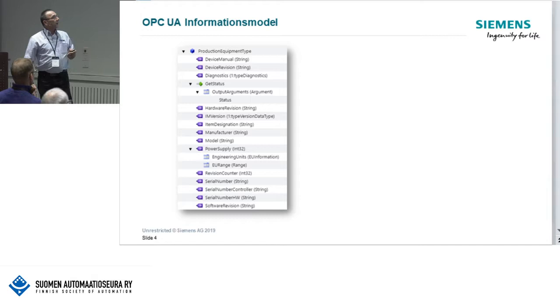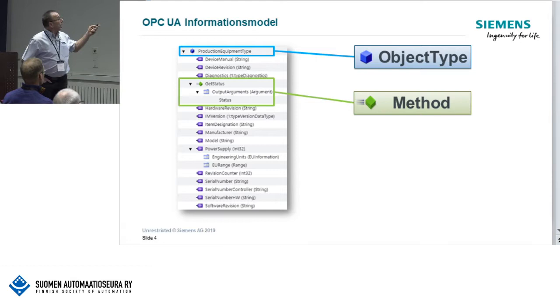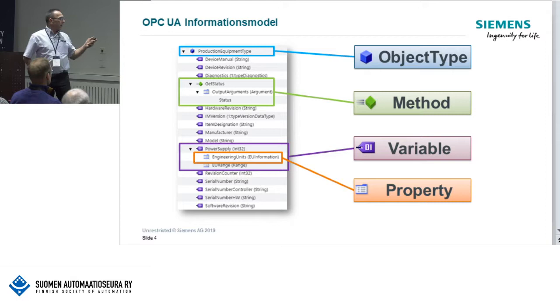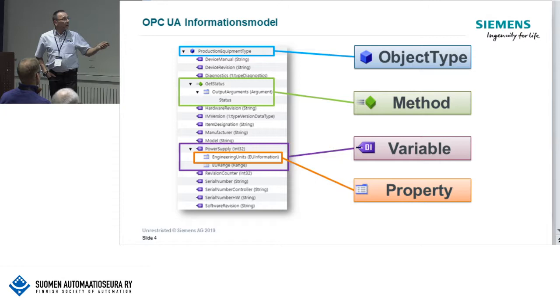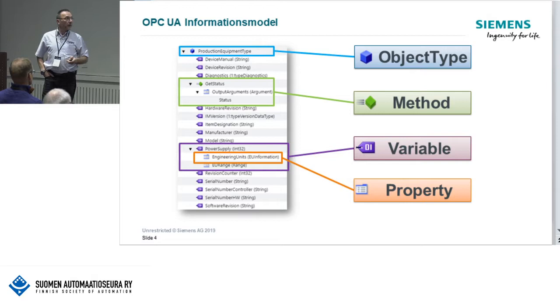In the information model it looks like this: here I take an example — we have a production equipment type, which is an object type. On this you get methods, variables, and of course you can define properties. These properties also carry meaningful information like engineering unit information, so they can tell you it's revolutions per minute, not millimeters per second, meters per hour, or pieces per day.